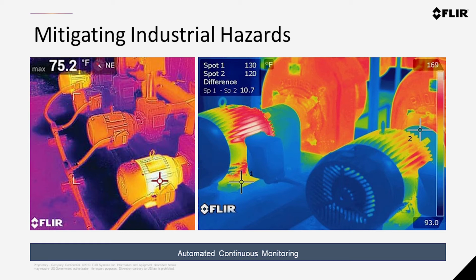You and I, none of us can see inside of that motor, so neither can the thermal imager. It will, however, show you accurate measurements of the external temperatures. And I think we heard it this morning, trend is your friend. If you're capturing data from these cameras, whether it's handheld inspections or continuous monitoring, capture that data, putting it in a database, a historian, an enterprise asset platform, something like that.